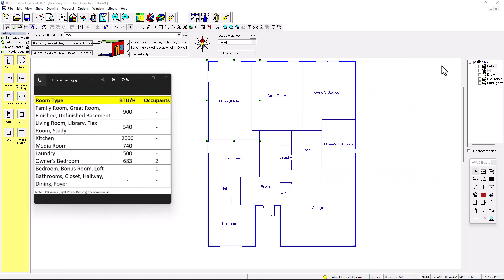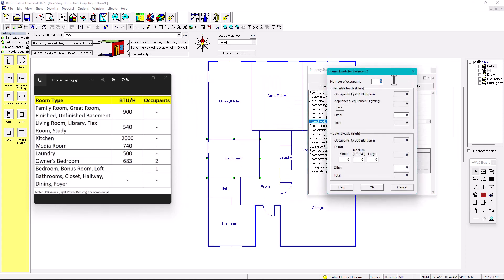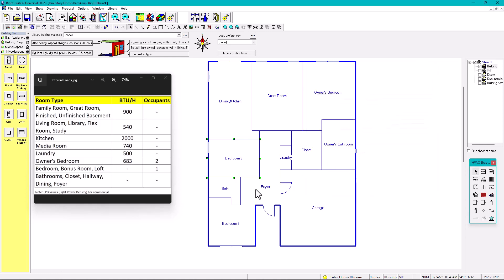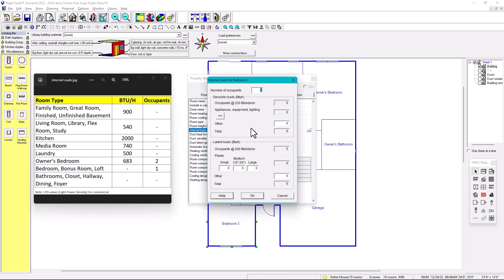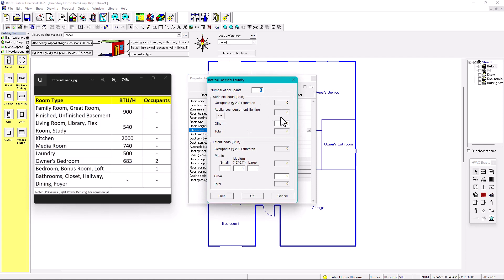For a bedroom, set one occupant. By default, one occupant gives you 230 BTUs sensible and 200 BTUs latent — that's from Manual J and it populates automatically. When you put one occupant, don't add any appliance load; leave it at zero. Do the same for bedroom three — one occupant.